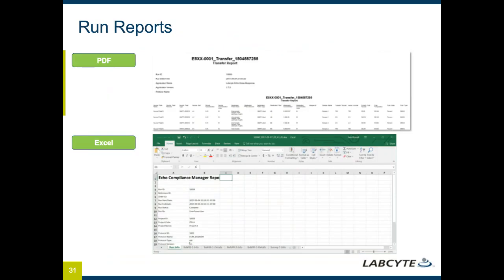As I mentioned, the instrument tracks a lot of information as it goes through a run, and that information is captured in the SQL database itself and can be output from the software in one of two formats. If you want a format that cannot be changed, you have the option to output that as a PDF. And the nice thing is the system tabulates all of the data for you. Or you can output that as an Excel file if, for instance, there's any downstream analysis that might go into, or whether that might get transferred into a LIMS system, for example. And there, the different reports that the Echo produces are situated on different Excel worksheets. So there's different tabs for each of those reports.